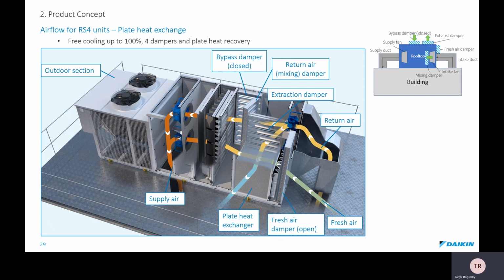Here we have fresh air going in through the fresh air damper and across the plate heat exchanger. On the other perpendicular side, we have extracted air entering the cross-flow heat exchanger. After the heat recovery exchange happens from both streams, the air is mixed with the remainder of the return air in the mixing chamber. The next stage is a sequence of multiple filtration stages, after which the air goes through the coil and is distributed to the air-conditioned space by the supply fans.